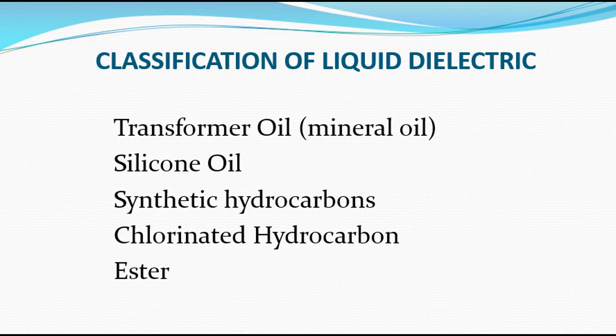Now, I also want you to remember that liquid dielectric acts as a heat transfer agent in a transformer. That is what I want you to understand. Liquid dielectric acts as a heat transfer agent in a transformer. The most important fact that affects the electrical strength of an insulating oil is the presence of water. What I'm trying to explain here is the negative effect on the liquid dielectric, which is water.